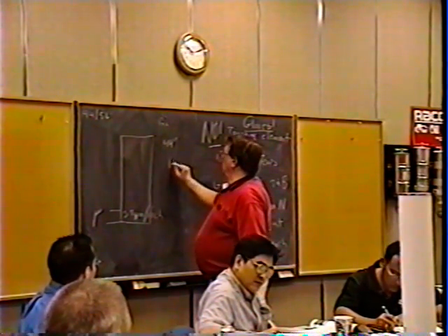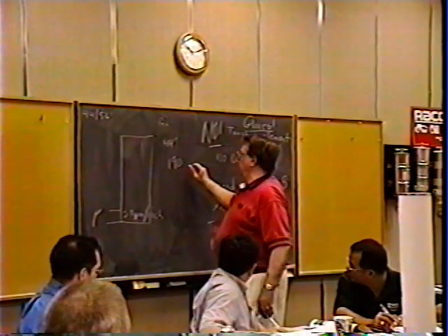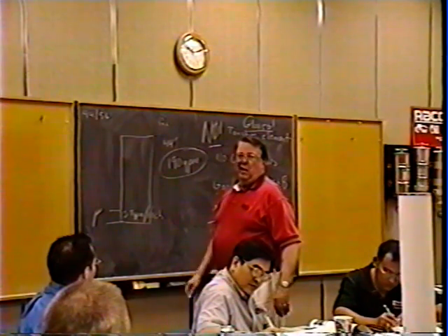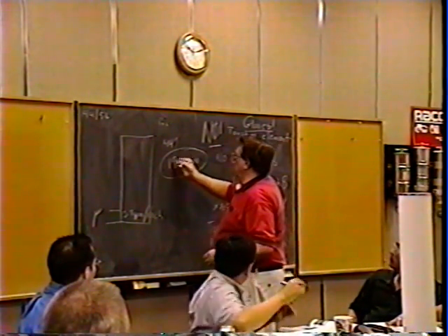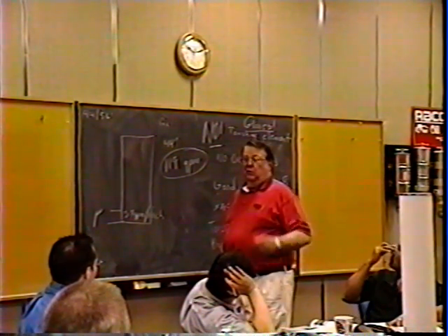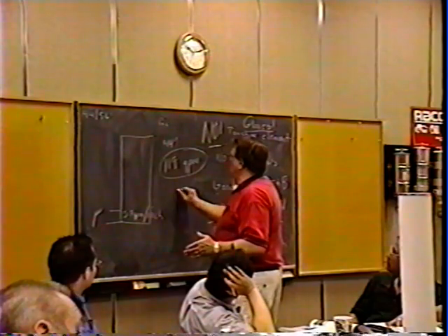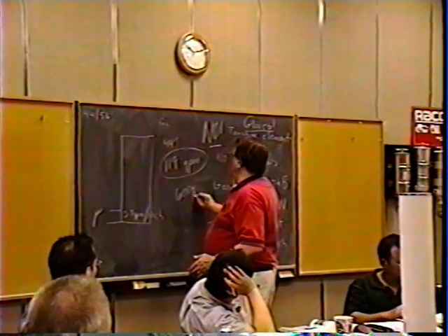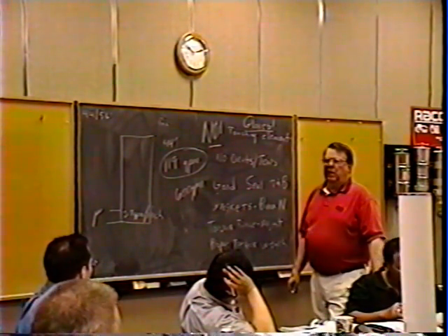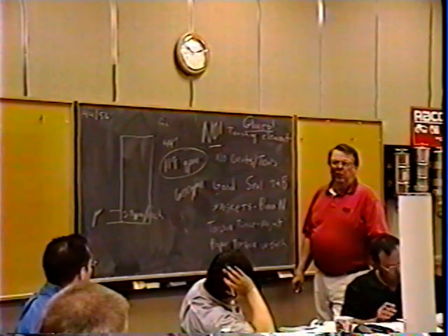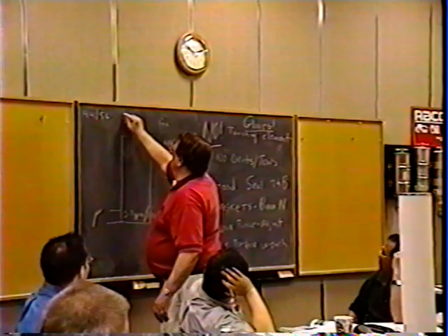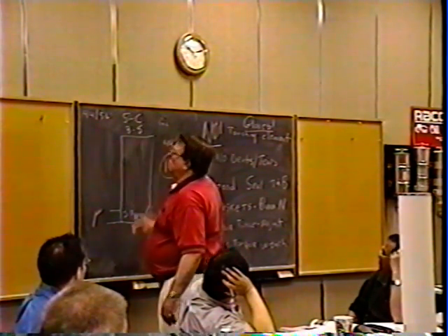Okay, so that one element can flow 119 gallons per minute. Now, let's say I want to build a housing and I want to flow 600 GPM. How many coalescers am I going to need? 5. Number 5. Okay, and then normally in a 5 box, you would have 5 coalescers and 3 separators.